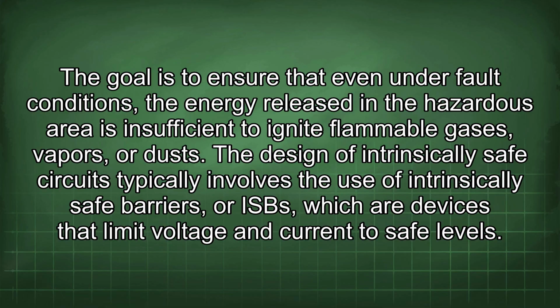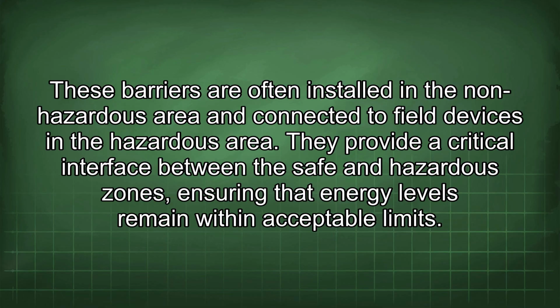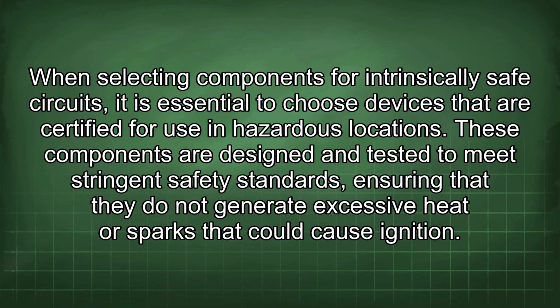The design of intrinsically safe circuits typically involves the use of intrinsically safe barriers, or ISBs, which are devices that limit voltage and current to safe levels. These barriers are often installed in the non-hazardous area and connected to field devices in the hazardous area. They provide a critical interface between the safe and hazardous zones, ensuring that energy levels remain within acceptable limits. When selecting components for intrinsically safe circuits, it is essential to choose devices that are certified for use in hazardous locations. These components are designed and tested to meet stringent safety standards, ensuring that they do not generate excessive heat or sparks that could cause ignition.